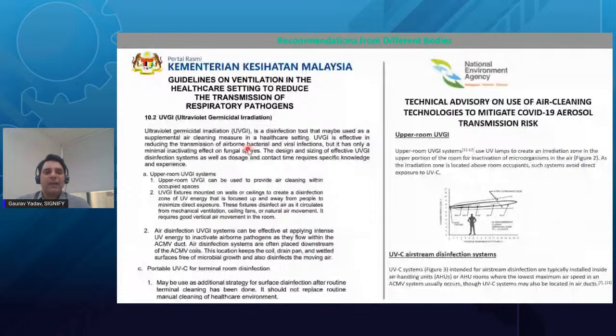If I talk about KKM Malaysia, they are saying that to improve ventilation in the healthcare setting, you can use UVGI. UVGI stands for ultraviolet germicidal irradiation. You can implement UVGI for the upper room, or within the ducts or within the AHUs, so that you can avoid airborne transmission. Or you can also use portable UVC for terminal room disinfection.